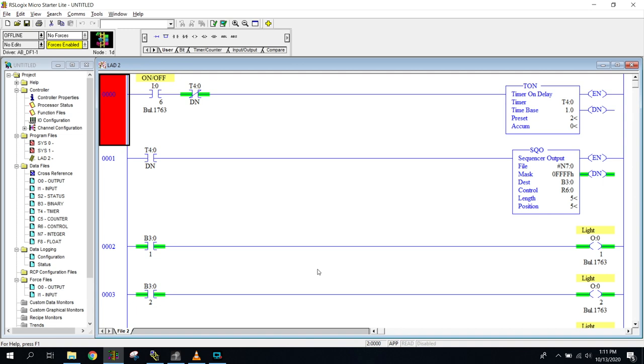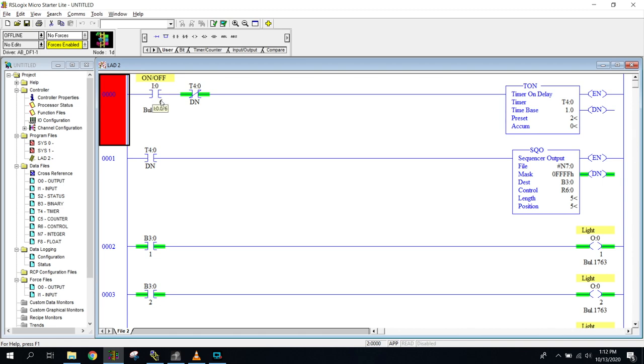So it's actually pretty simple to do. All we've done is we've replaced—remember we used to have a push button over here on our rung one that would move our sequencer step through step. Instead of doing that we have a free running timer right up here. On our free running timer we have an on-off switch. This is a latching button. You could easily put a push button in here if necessary. All you'd have to do is do a little drop down around it with an EN bit to latch it on whenever the timer gets started.